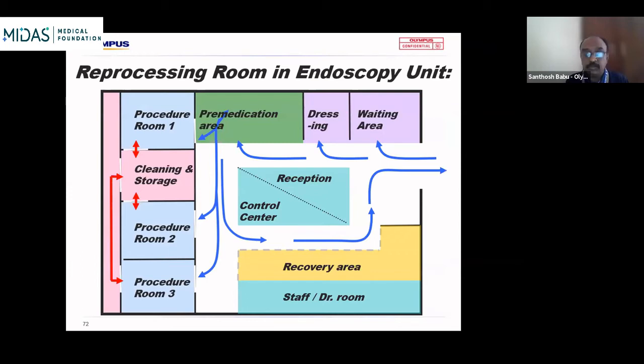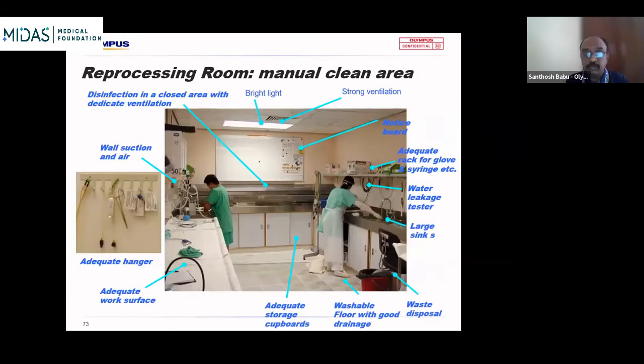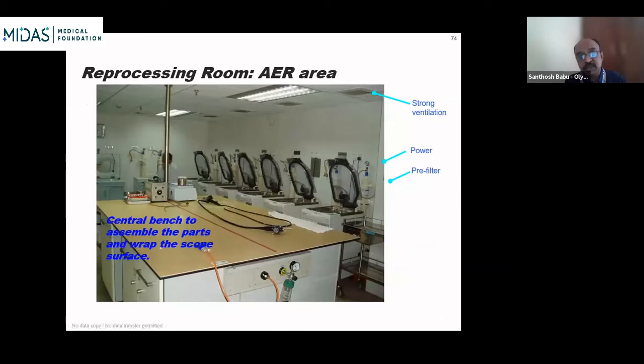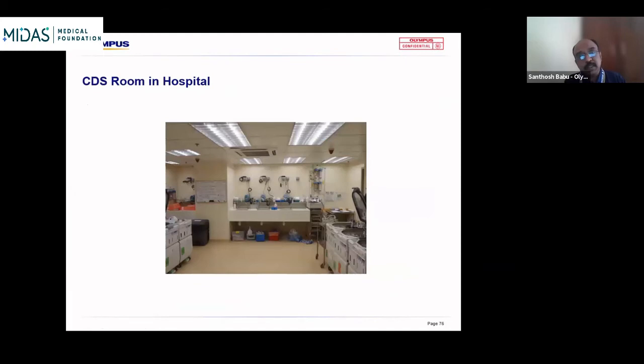This is one way of building up your endoscopy reprocessing area, sequential, moving from one end to the other. A dirty scope comes in, you do the manual cleaning, then the disinfection, and then the rinsing and drying. That is the ideal situation. The same layout can be used with automatic washers, but you still need some place for manual cleaning and then the automatic washer. Here are a couple of photos from a couple of institutes.